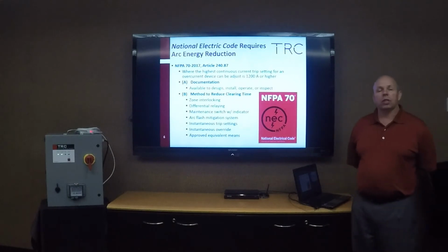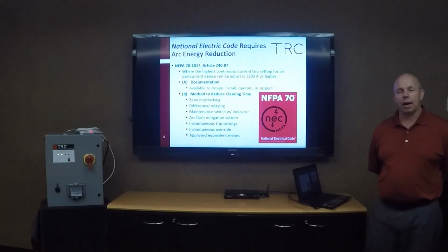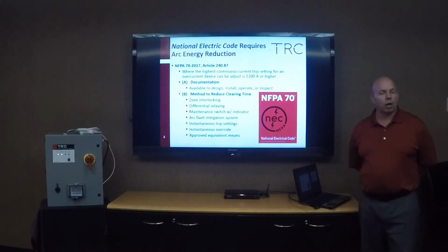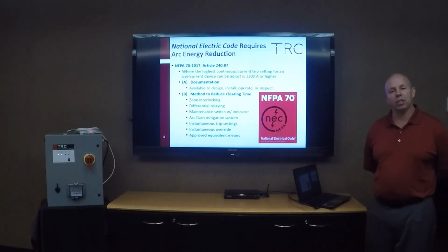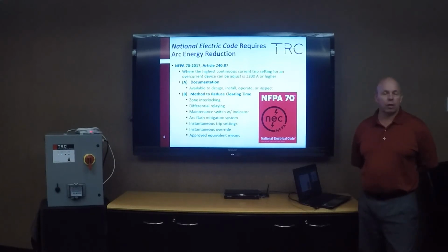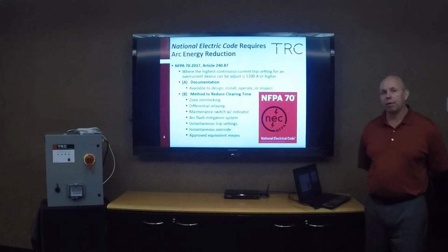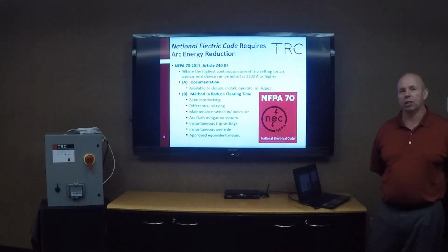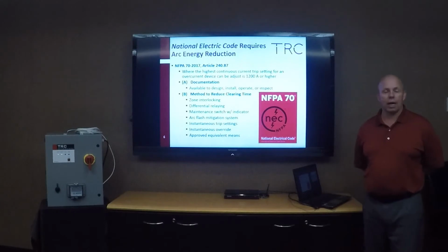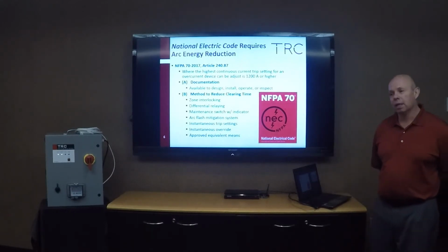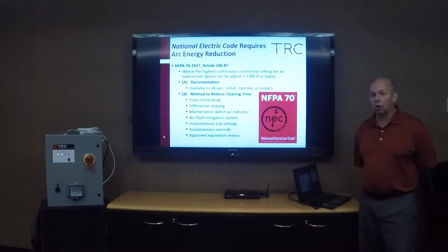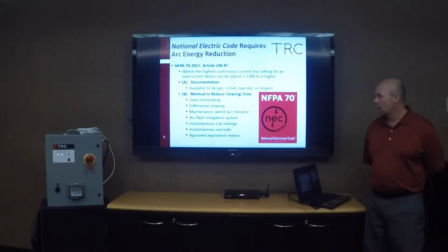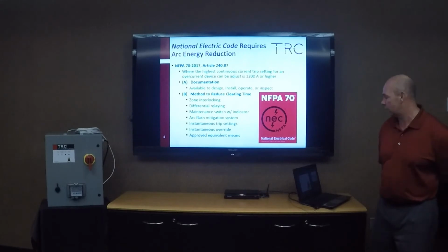In the 2014 version of the National Electric Code, Article 240.87, they introduced some requirements associated with arc flash and mitigation of those systems. So anytime we're looking at a breaker that's 1200 amps or greater, we're now required to do something to mitigate the incident energy associated with people that could be working on or near that energized electrical system. And the methods of arc flash mitigation include zone interlocking, differential relaying, a maintenance switch with indicators, arc flash mitigation, instantaneous trip, instantaneous override, or any other type of approved method to reduce the amount of incident energy.